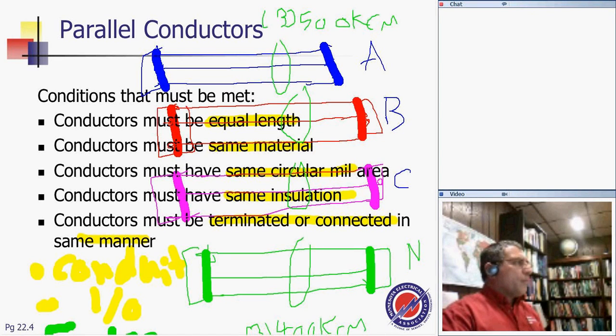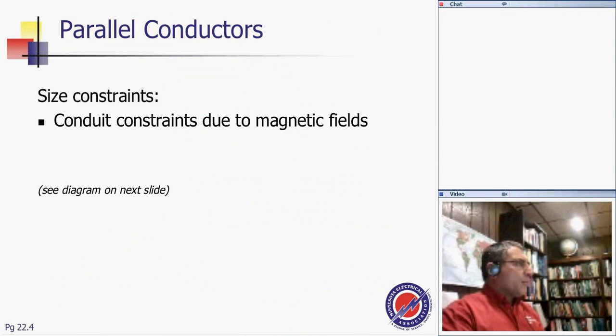Any questions about the rules for paralleling conductors? So basically, the rules for paralleling conductors: I emphasize same length, same material, same circular mil, same insulation, same termination, same conduit type, and not less than 1 aught. Not less than 1 aught. That's the rules for parallel conductors.